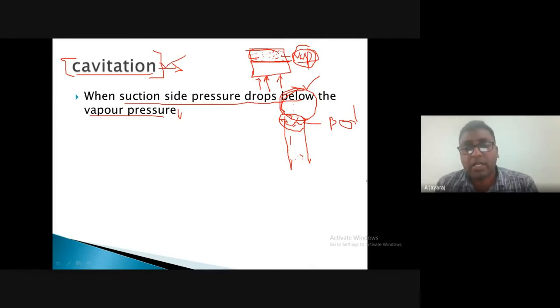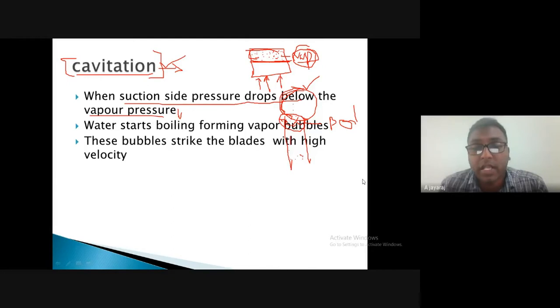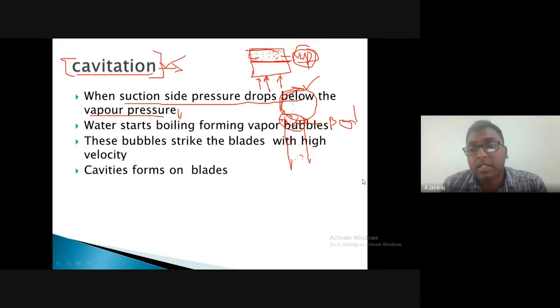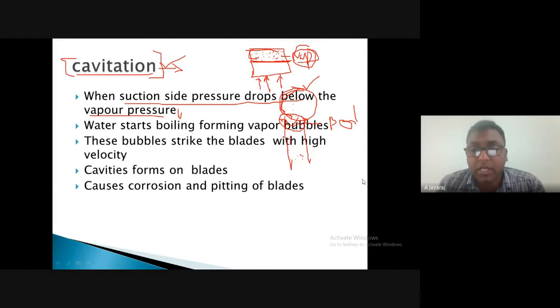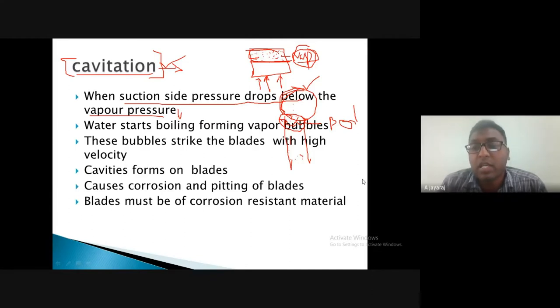Water starts boiling, forming vapor bubbles when pressure drops below vapor pressure. These bubbles strike the blades with higher velocity, forming cavities on the blades — leading to corrosion and pitting that continuously damages blade and casing surfaces. To avoid cavitation, ensure suction pressure does not fall below vapor pressure, and blades and casing must be made with suitable corrosion-resistant materials like aluminium or stainless steel.